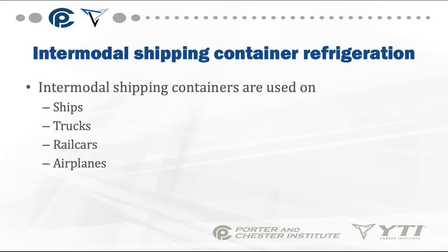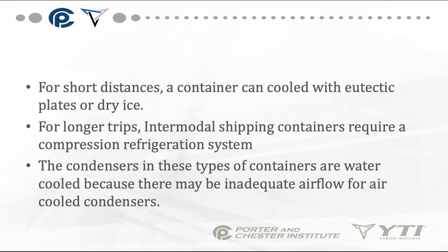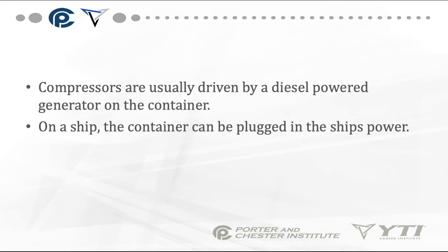Intermodal shipping containers are used on ships, trucks, rail cars, and airplanes. For short distances, a container can be cooled with eutectic plates or dry ice. For longer trips, intermodal shipping containers require compression refrigeration systems. The condensers in these containers are water-cooled because there may be inadequate airflow for air-cooled condensers. Compressors are usually driven by a diesel power generator on the container, but on a ship, the container can be plugged into the ship's power supply.